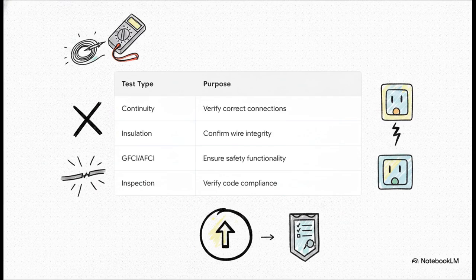First up is a continuity test using your multimeter. This ensures all your connections are solid, unbroken, and properly made. Next is an insulation resistance test, which confirms that no wires are frayed and secretly leaking current into the surrounding wooden studs. Then you've got to test your GFCI and AFCI outlets using their built-in test features. You need to know they will instantaneously trip in a life-threatening situation.